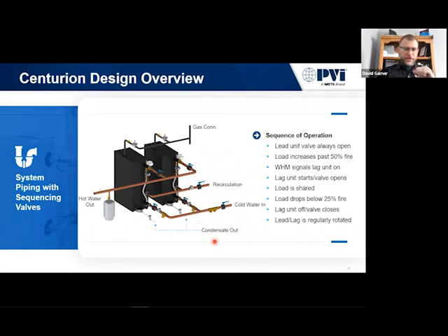Let's say that there's a load on the system and it starts to increase and only this unit here is fired. Once it hits about 50%, it's going to go, hey, my load's increasing. I'm a water heater. I need to react and make sure I give hot water now when people want it and need it. It's going to send a signal over to the next unit. It's going to fire, bring itself up to temperature, then open that valve before any water goes out into the system. And the reason we do that is we want to eliminate any cold water or hot water sandwich effect that would happen if we just opened this valve and ran water through the unit before it's had a chance to fire and come up to set point. We don't want to see these temperature fluctuations.